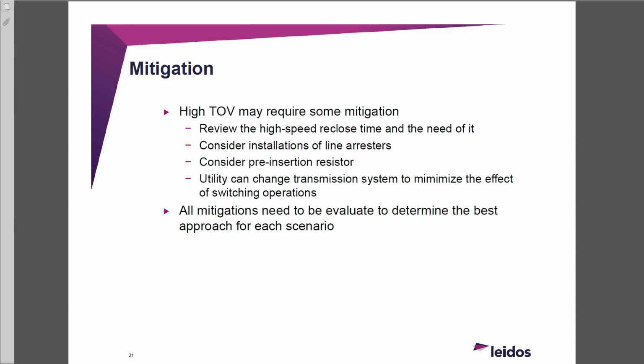Henry asked: do you study the case where, if you reclose your line and have a TOV, and you open the line during the TOV, you might end up with more than one per-unit trapped charge in the end? Do you study those cases? So you open, you have the trapped charge around one per unit, then you reclose, and for whatever reason you open again during the TOV. No, we didn't test that—we just tested closing with the trapped charge.